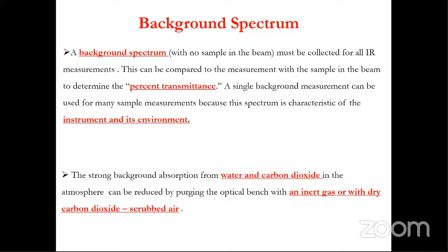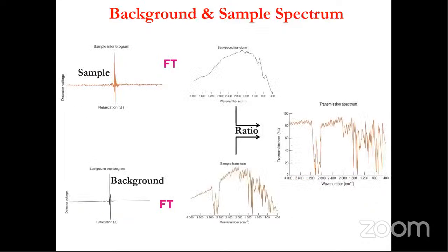A single background measurement can be used for many sample measurements because this spectrum is characteristic of the instrumentation and environment. A strong background absorption from water and carbon dioxide in the atmosphere can be reduced by purging, and an inert gas or dry carbon dioxide-scrubbed air can be used. So we take the Fourier transform of the sample and of the background, and we see the transmission spectrum.